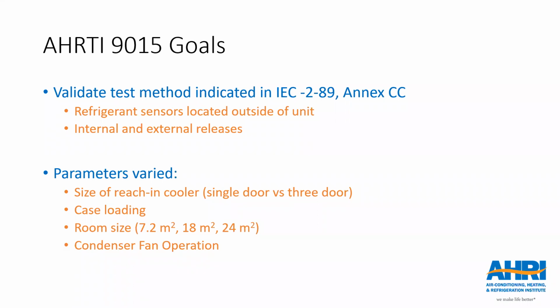There were also three different room areas varied, corresponding to the minimum room area specified in Annex CC for the refrigerant charges. And finally, we'll look at the effect of condenser fan operation during both internal and external releases. Next slide, please.